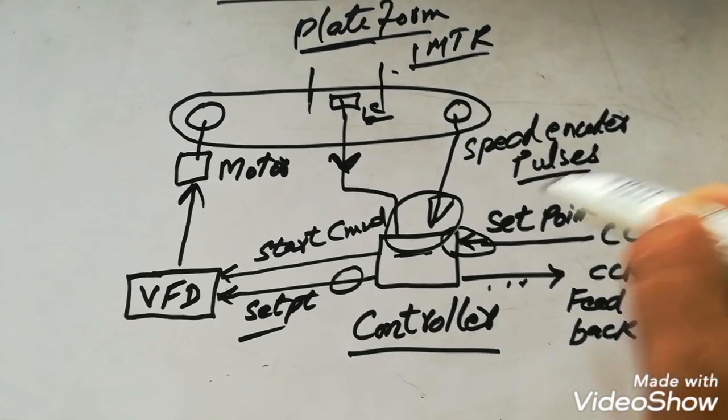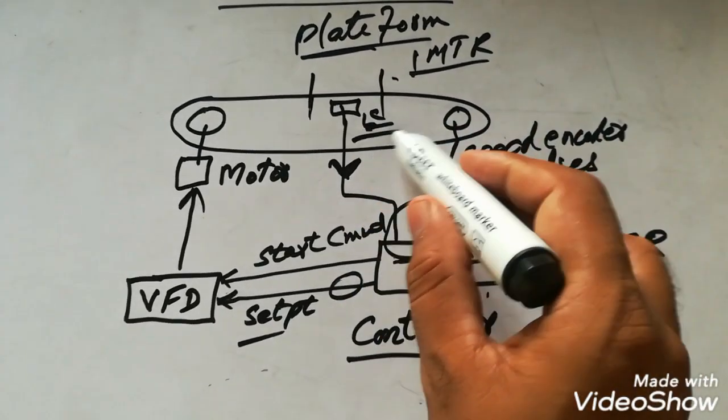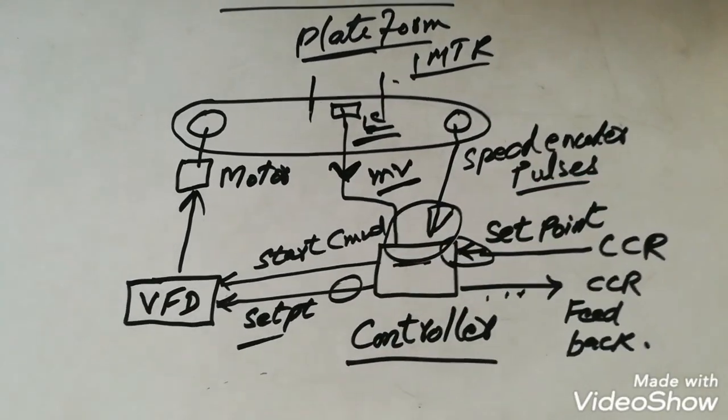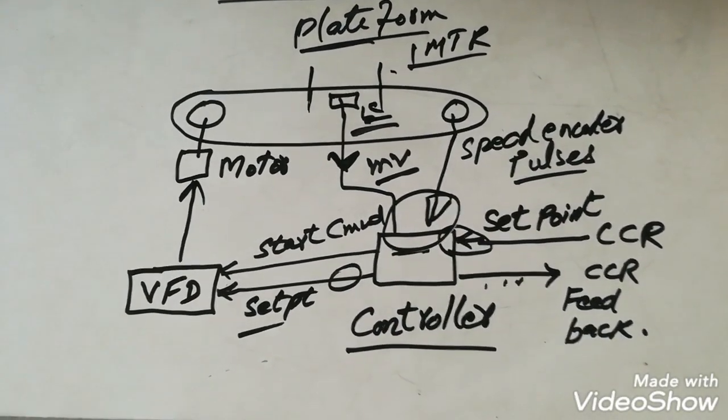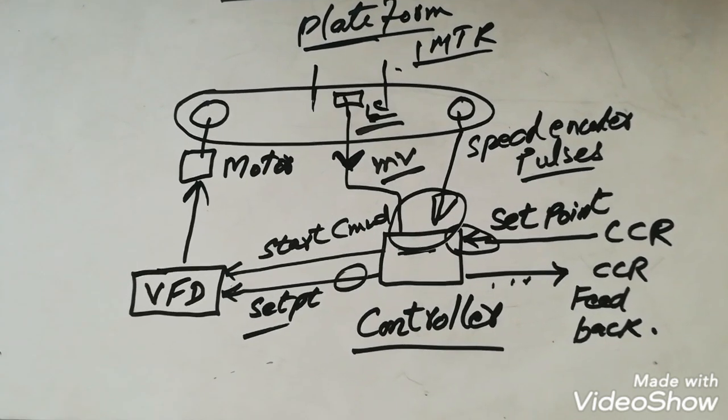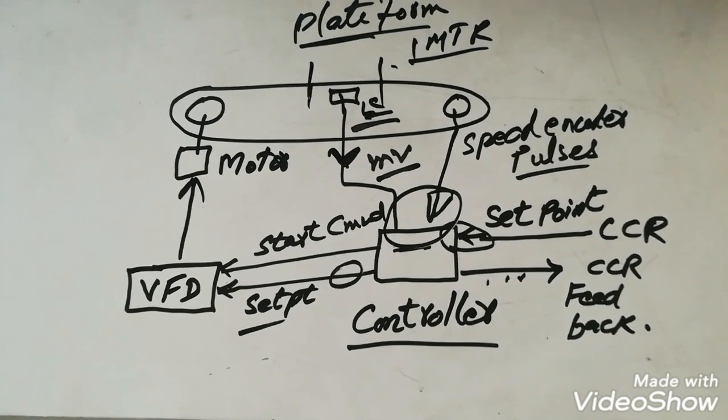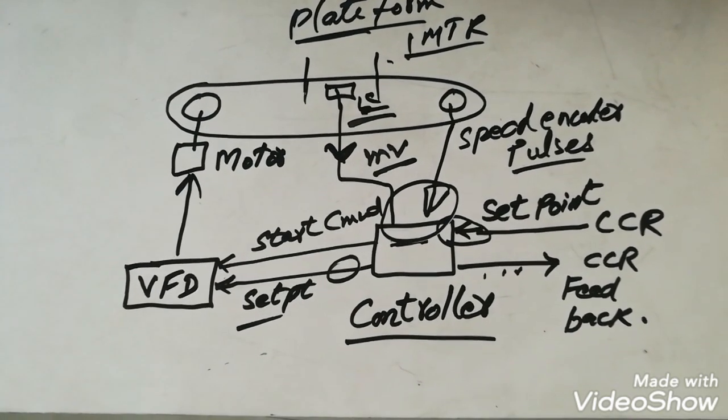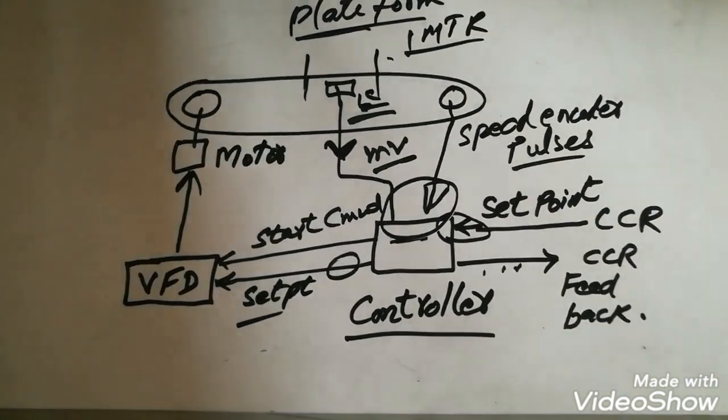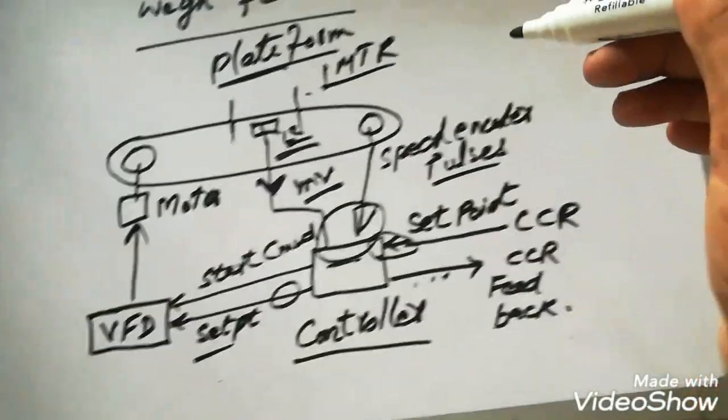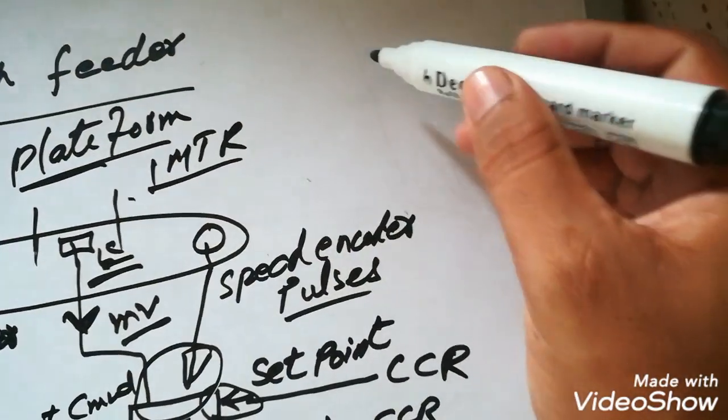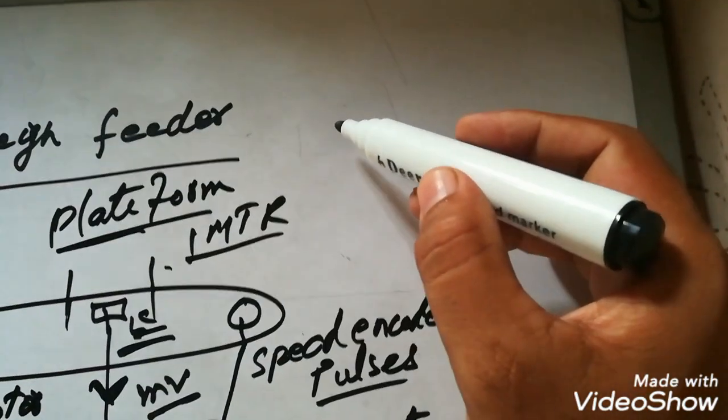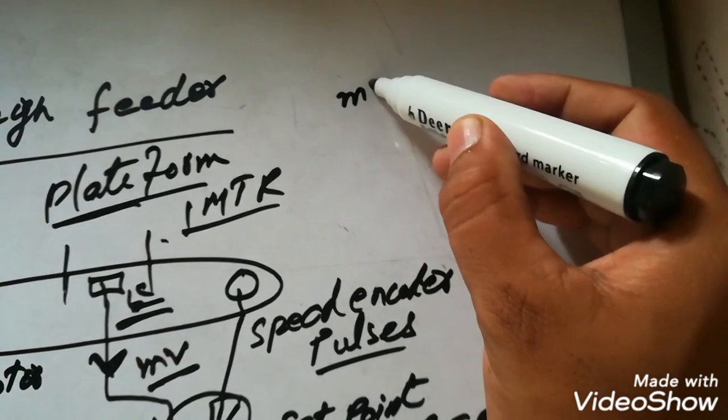Speed encoder will give pulses. It is just a proximity switch and load cell will give us the millivolt as per the load. So these are all the inputs and outputs of the weigh feeder. There may be also alarms from the controller to the operator.